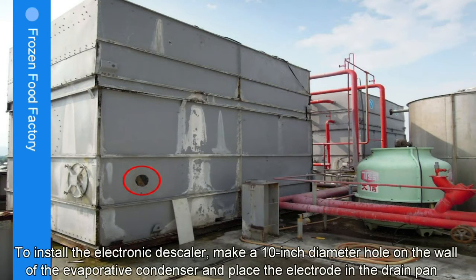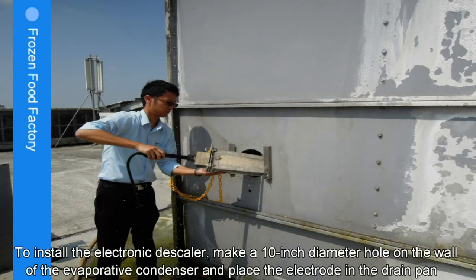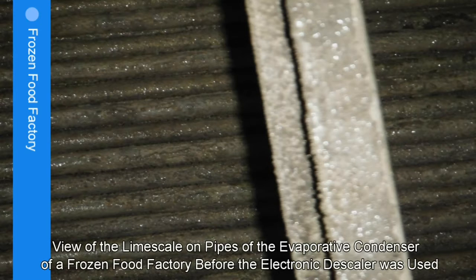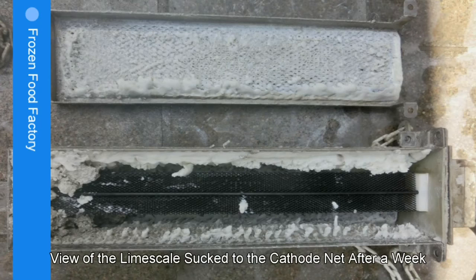To install the electronic descaler, make a 10-inch diameter hole on the wall of the evaporative condenser and place the electrode in the drain pan. View of the limescale on pipes of the evaporative condenser of a frozen food factory before the electronic descaler was used. View of the limescale sucked to the cathode net after a week.